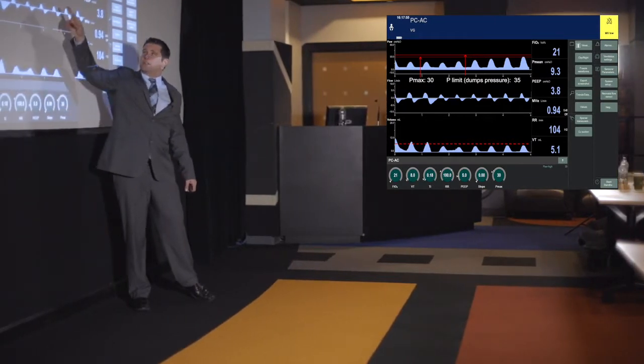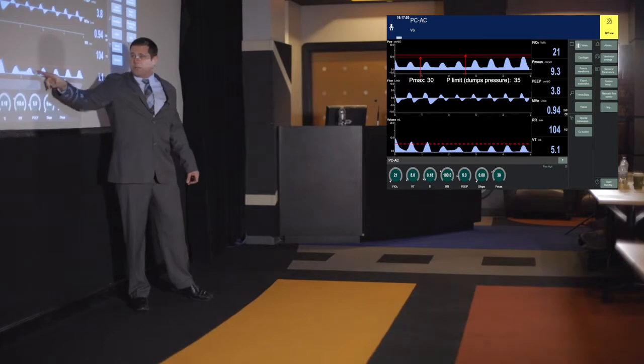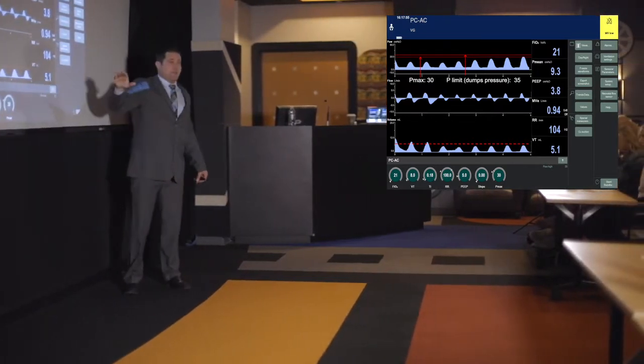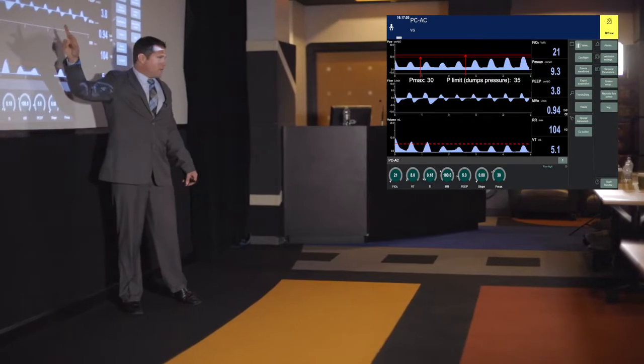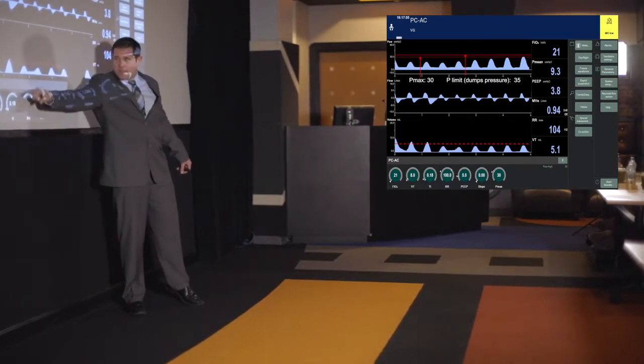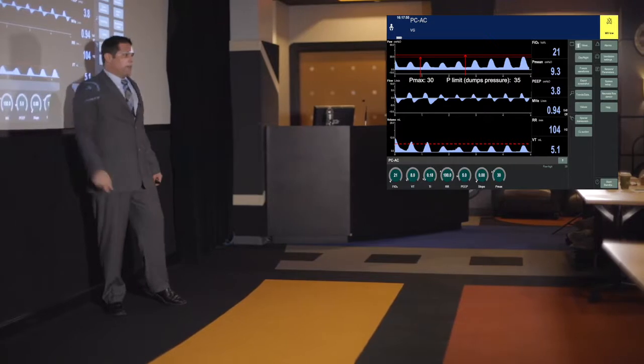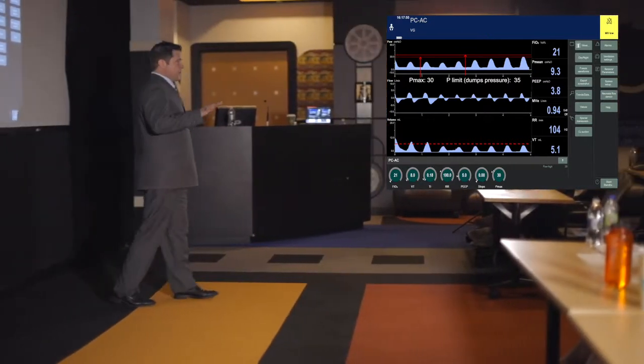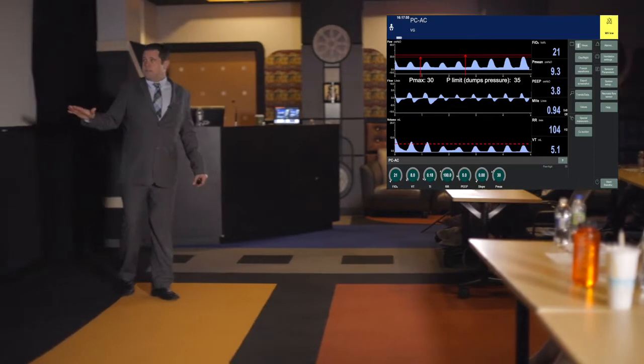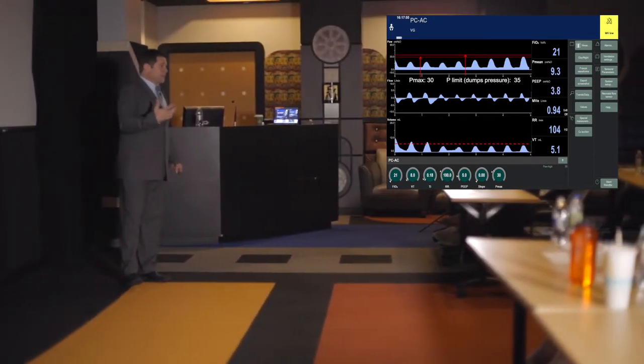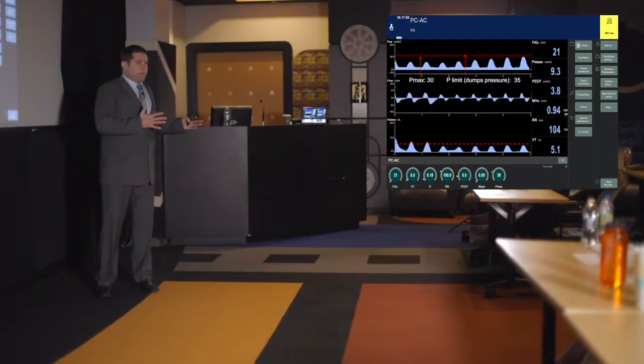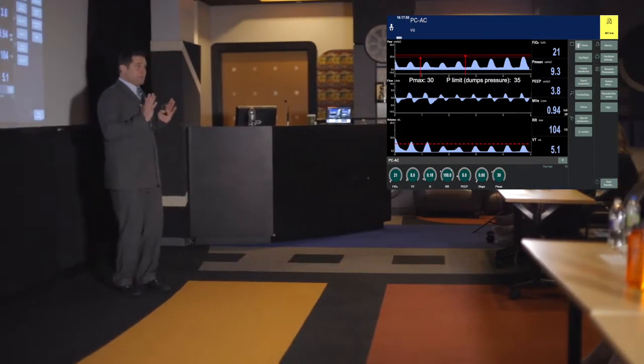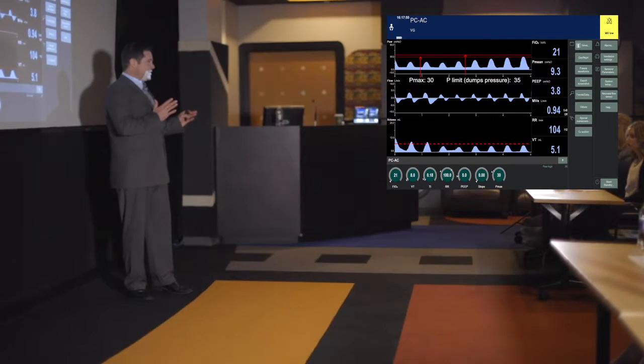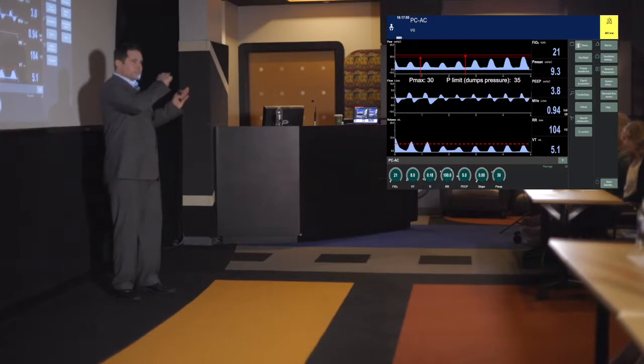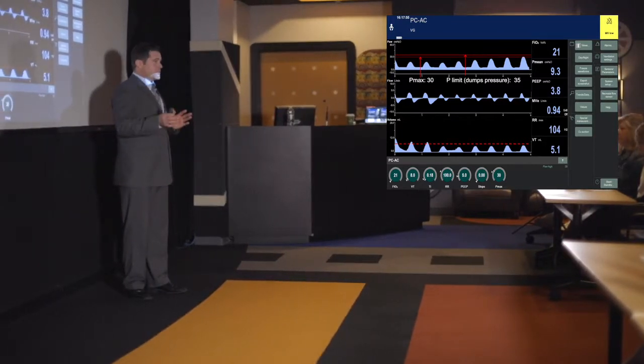Maybe, actually, we didn't reach the pressure in this one, but what it's done is it's weaned the pressure down a little bit. So in the background, maybe we met that excessive tidal volume that's set at 150% of that. So that's why we had such a drastic drop in the pressure, because the gain is a little bit different. You're going to have a higher drop in pressure. But also in these modes of ventilation nowadays, there are separate algorithms going on all of the time, different algorithms for when the baby's not breathing versus when the baby's breathing, and it tracks what the tidal volume is during spontaneous breathing, and has a different VG measurement in assist control if they're triggering versus not triggering.